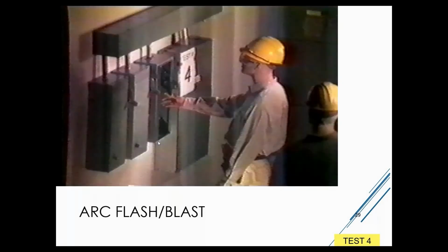Okay, so these are the still shots from that event that you just saw. This is the early onset of it, the beginning of it. These are in about 1/10 of a second intervals. And then you can see the intense light now that's coming from it. You can see it took the wireway cover off. They're not really hardened bolts holding those; they're kind of soft, smaller screws that hold the wireway cover on. So you can see it actually took the wireway cover off of the equipment.